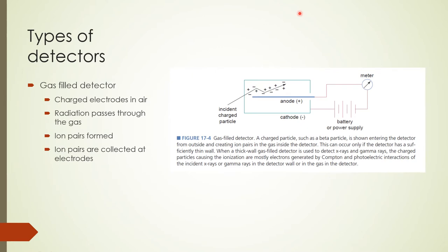Now let's talk about different types of detectors. We shall start with gas-filled detectors, then learn about scintillation detectors, semiconductor detectors, and some instruments using these types of detectors. A gas-filled detector is basically two charged electrodes in air. The electrodes are charged with a voltage depending on the region of operation. When the gas between the electrodes is ionized by radiation, ion pairs are formed. The positive ions are attracted to the negative electrode, and the negative ions are attracted to the positive electrode. A current flows between the electrodes and is measured and converted to the amount of ionization in air. The figure shows a simplified gas-filled detector with positive and negative electrodes, power supply, and a meter for measuring the amount of radiation.